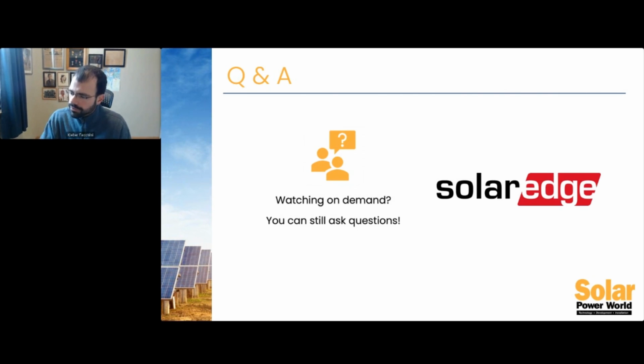As Varsha mentioned, our launch project is in a commercial establishment connected at 480 volts AC. The customer decided to use that because it is a ground mount behind the meter, with a hotel building, and the array is very far from the connection. So they like the 690 volts AC to deal with AC losses over the long AC run. They transmit 690 all the way to near the building, then step down from 690 to 480 volts, and then feed the building.